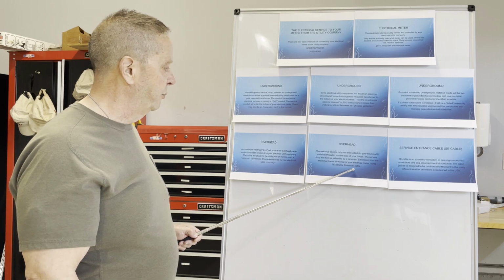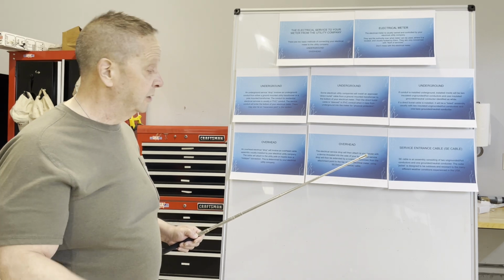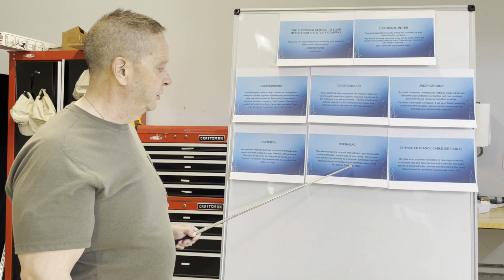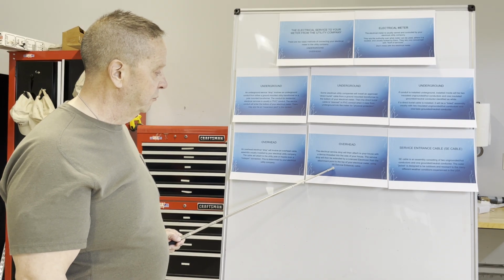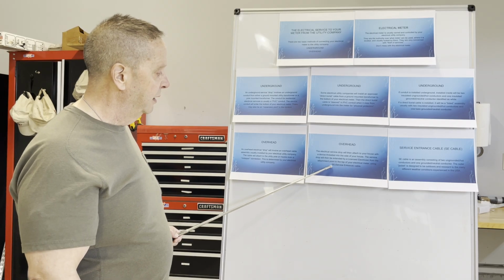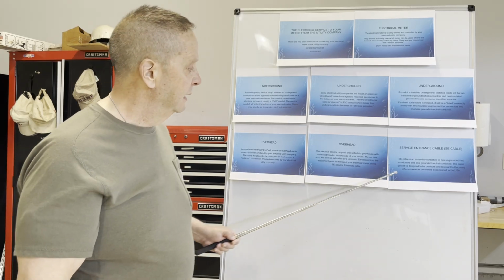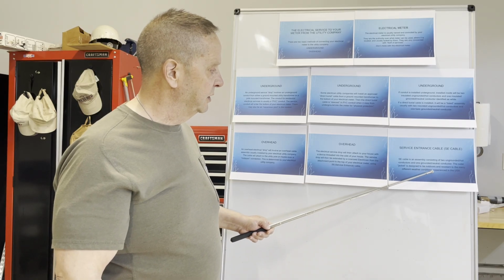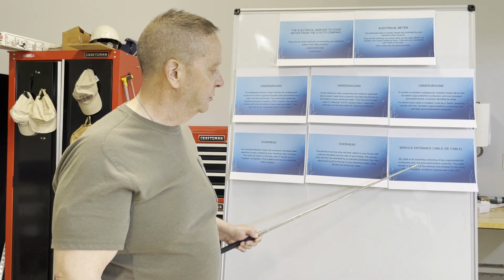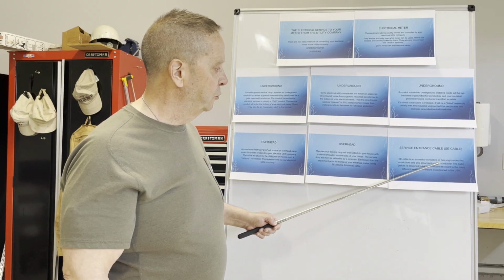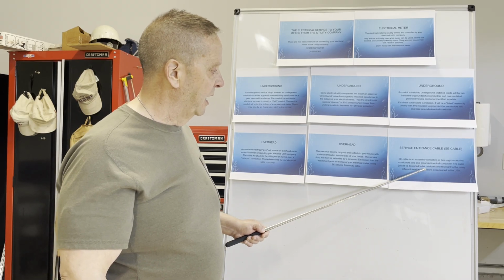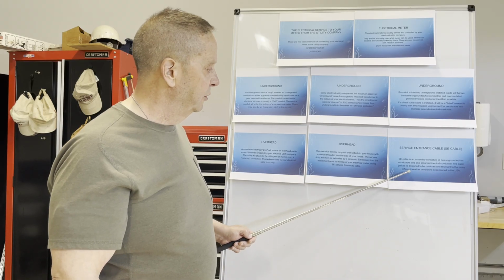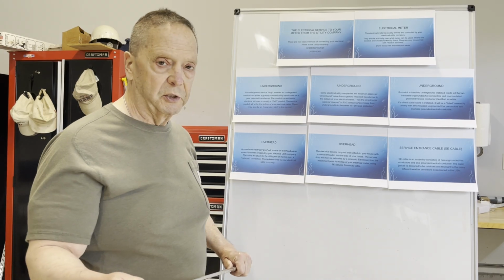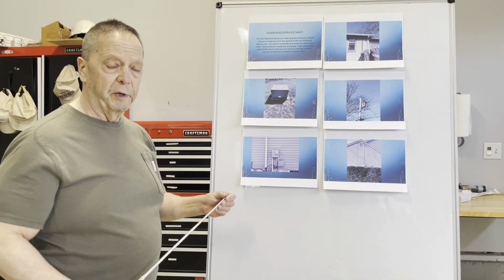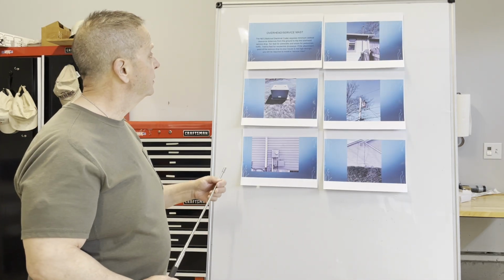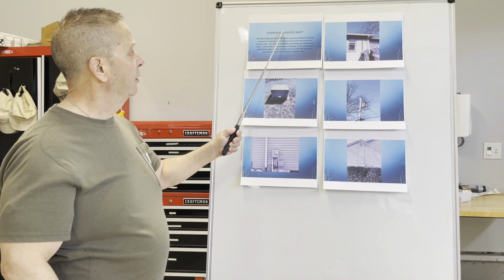The service drop will then be extended by a licensed electrician from the attachment point to the top of your electrical meter using what we call service entrance cable, otherwise known as SE cable. Service entrance cable is an assembly consisting of two ungrounded hot conductors and one grounded neutral conductor. The outer jacket is designed to be outdoors and resistant to the many different weather conditions experienced here in the United States. Continuing on with the overhead services, you may have what's known as an overhead service mast.